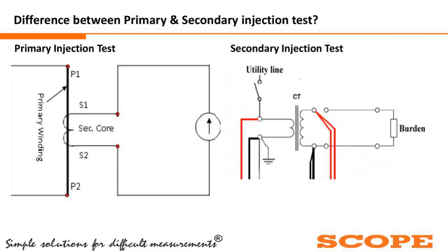Secondary injection means whatever parameters we are checking or whatever injection is done from the secondary side of the current transformer. Here you can see the CT core and the utility line — P1 and P2. In the secondary side we inject a small amount of current or voltage to check the excitation current or ratio. To check the ratio we inject some voltage from the secondary side and accordingly check whatever voltage appears from the primary side — but this is not a direct method to calculate the ratio of the CT. So secondary injection is an indirect method, whereas primary injection is the direct method to check the CT ratio relationship.